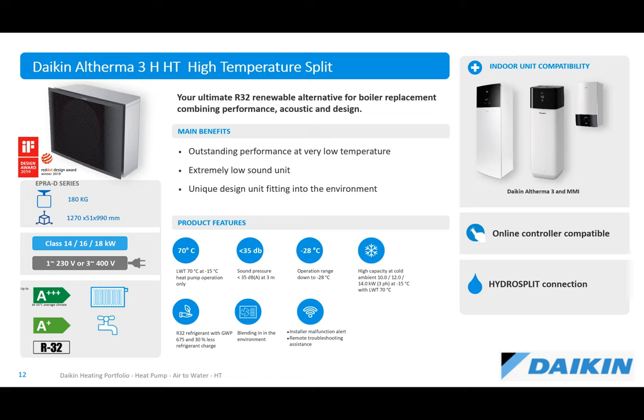So we don't have a huge market for high temperature heat pumps in Ireland, because when we're looking at retrofit, we're generally upgrading our buildings to make them more energy efficient, and therefore our low temperature heat pump range is actually suitable to match the building. So the high temperature is only used in very specific circumstances. If you had maybe a period house where you have old cast iron radiators that can't be replaced, or you just want to keep them, by taking out the boiler and putting in this high temperature split, you're getting a like for like system where you can still run those radiators at the same high temperature. So from that point of view, it's a really good solution.